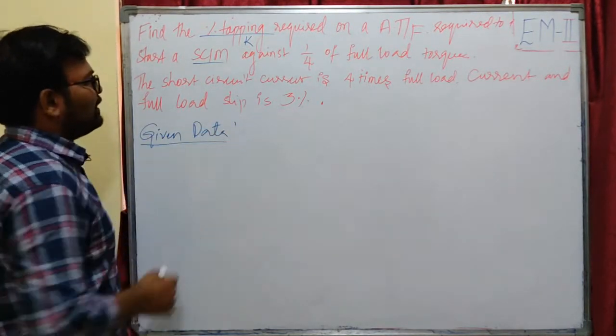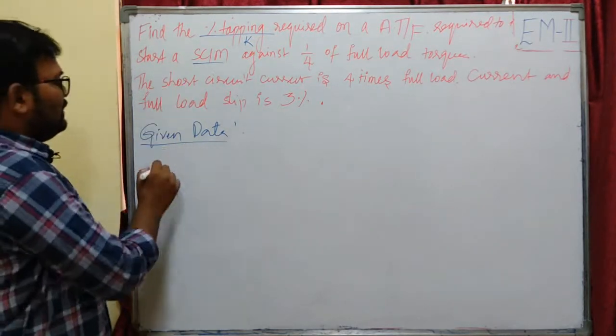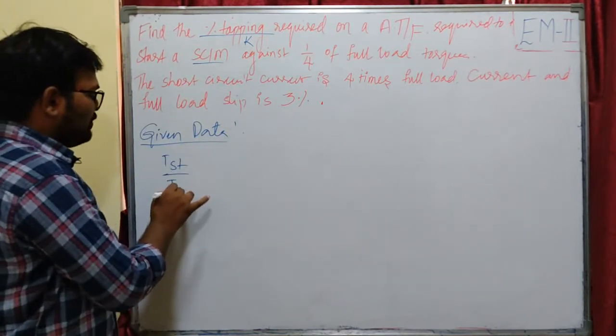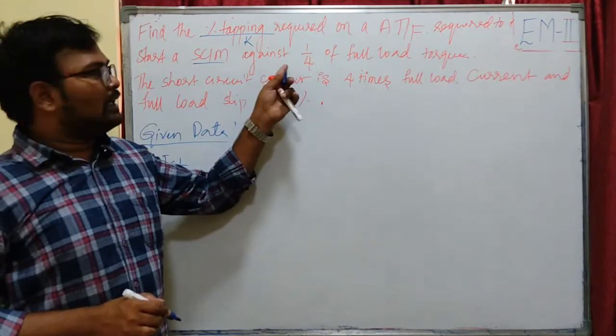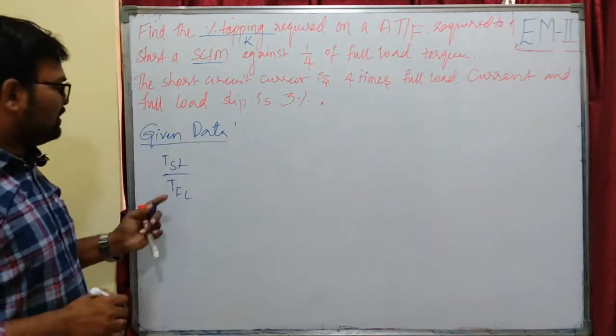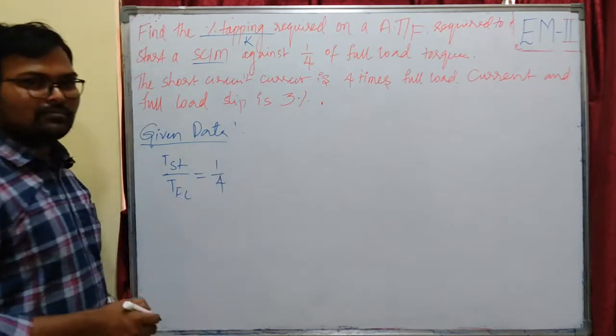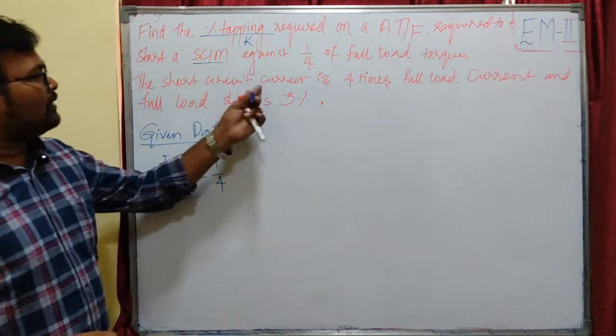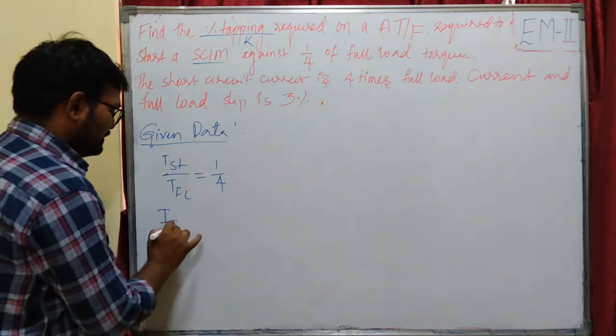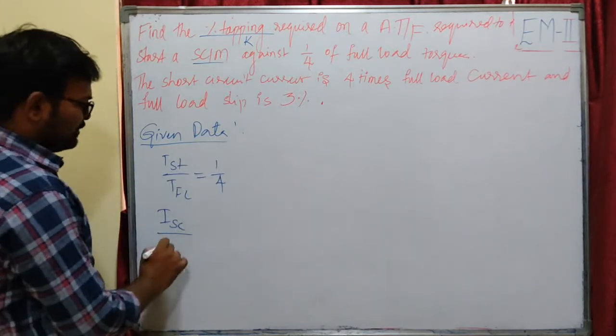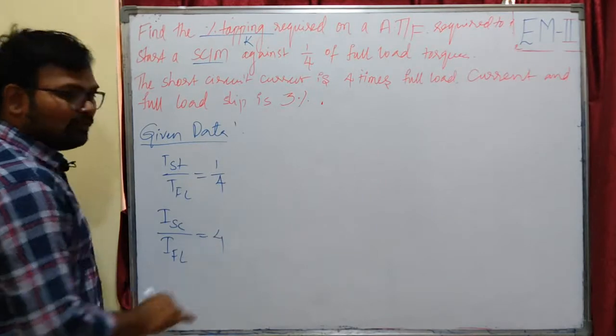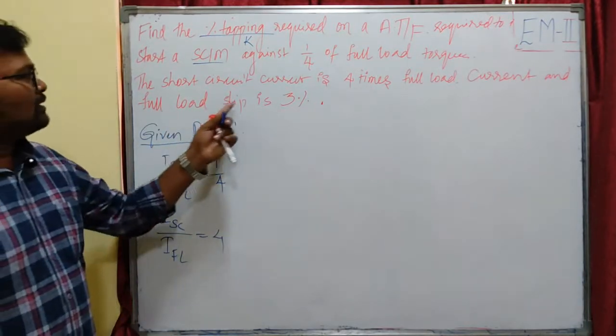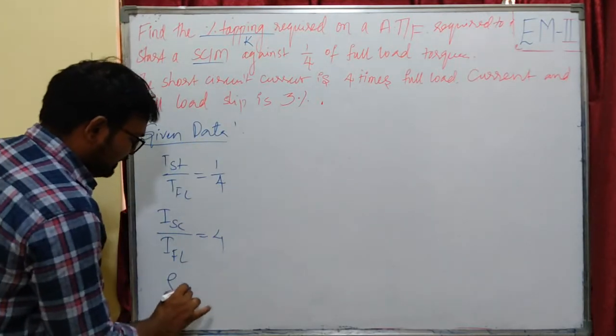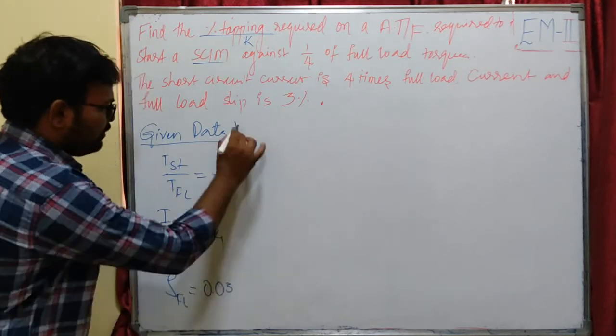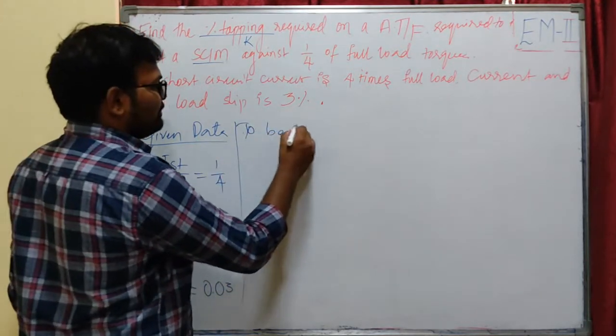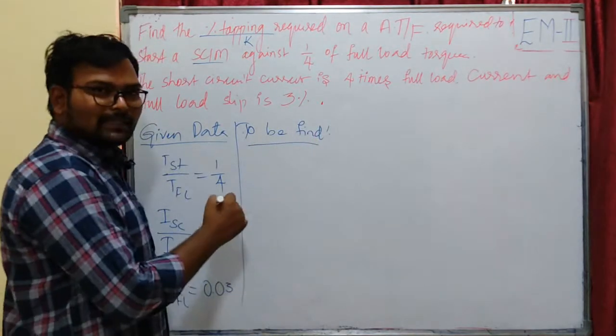Let us write the given data first so that you can understand what is to be done. The given data: starting torque to full load torque is 1/4, since we start the squirrel cage against 1/4 of full load torque. The short circuit current is 4 times full load current, that means ISC by IFL is 4. The full load slip is 3%, that means slip at full load SFL is 0.03. Now what is to be found? To be found is the percentage tapping.